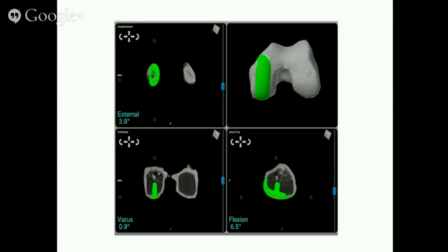to the depth of cut that's indicated. Then the robotic arm will resist his movement and stop him going past the agreed bone removal plan. If he tries to push past that haptic wall, the system will shut down.